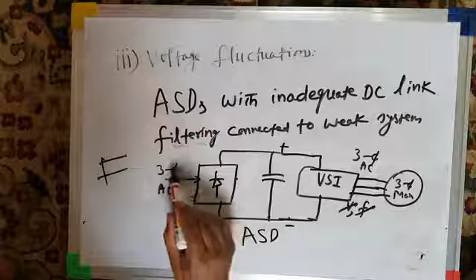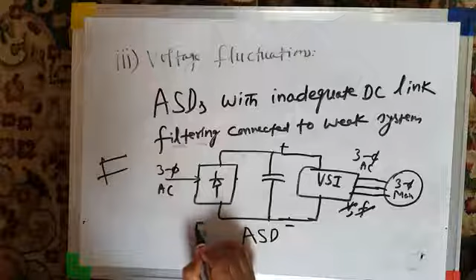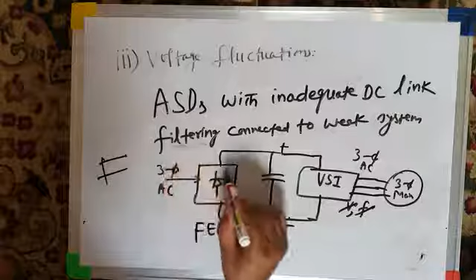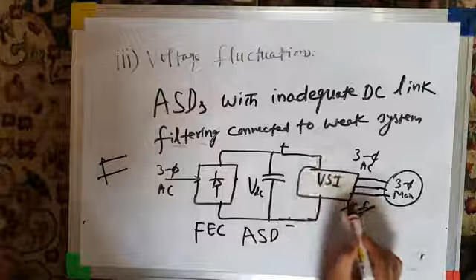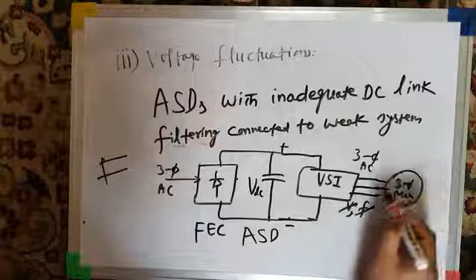Inverter basically converts DC into AC. So first of all, you have to create this DC link. How do you create this DC link? By converting what is available to the industries. It's three-phase AC, so you have to use a three-phase AC to DC converter. It's called the front-end converter, FEC, because it is on the front-end side. It converts three-phase AC into DC. And then to remove the ripples in the DC output voltage, VDC, you connect a filter capacitor. And then this VDC is converted by this three-phase voltage source inverter into three-phase AC with variable voltage, variable frequency, which is then used for the speed control of three-phase motors or three-phase induction motors.